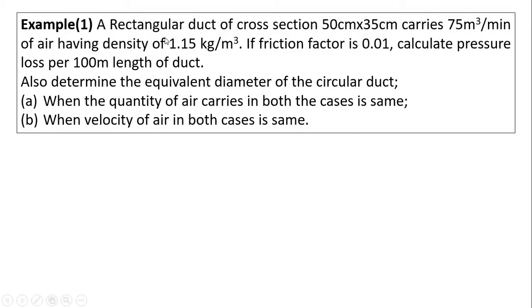The first numerical is as follows: a rectangular duct of cross section 50 centimeter by 35 centimeter carries 75 meter cube per minute of air having density 1.15 kg per meter cube. If the friction factor is 0.01, calculate the pressure loss per 100 meter length of duct. Also determine the equivalent diameter of circular duct when (a) quantity of air carried in both cases is the same, and (b) velocity of air in both cases is the same.